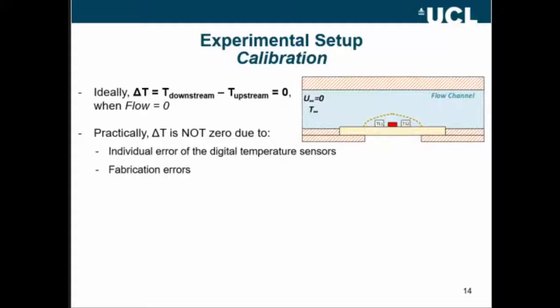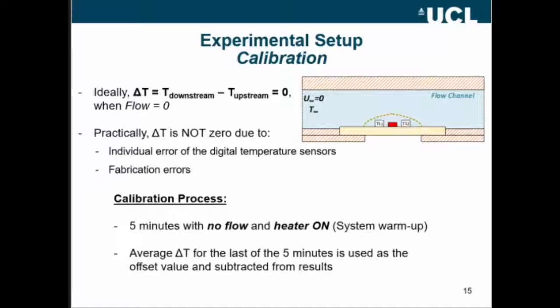The thermal conductance from the heater to the temperature sensors is not the same. So really simple, we just turn the heater on for five minutes, more than enough time for the system to warm up, and we take the last minute to calculate an offset value that we can subtract from the results.